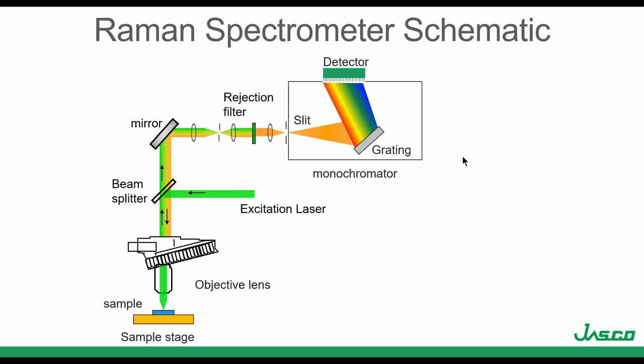This is the schematic of a Raman spectrometer. Today I want to emphasize three different parts: the objective lens, the sample stage, and the detector. The light source in a Raman spectrometer is the laser. The laser goes to a beam splitter where the light is reflected, then goes to the objective lens. It is reflected and creates the Raman signal. This Raman signal goes back, and this time it's transmitted through the beam splitter, goes to a mirror, then a rejection filter. The light is dispersed in a grating and then goes to the detector.